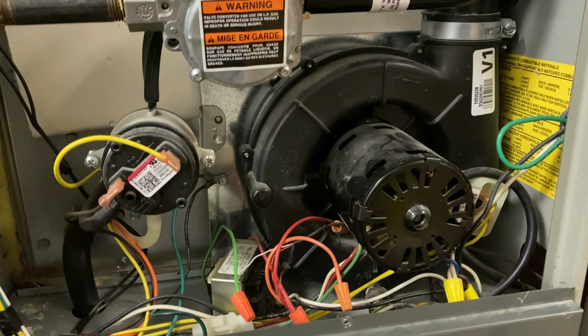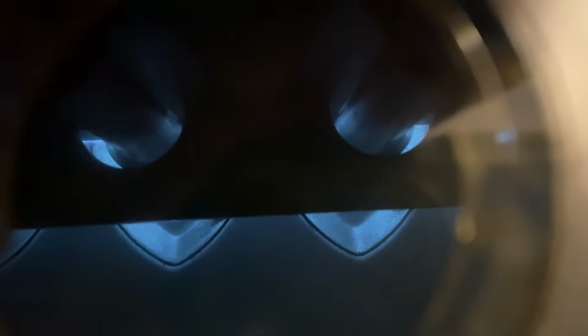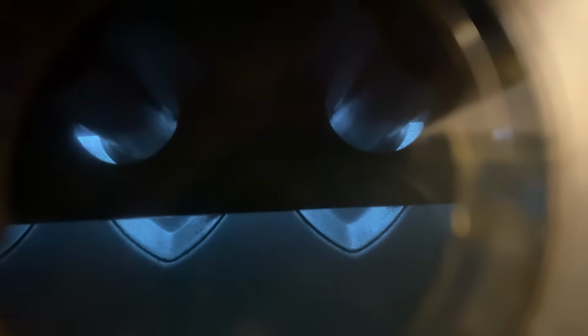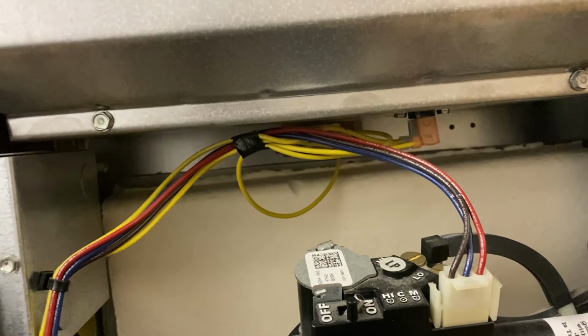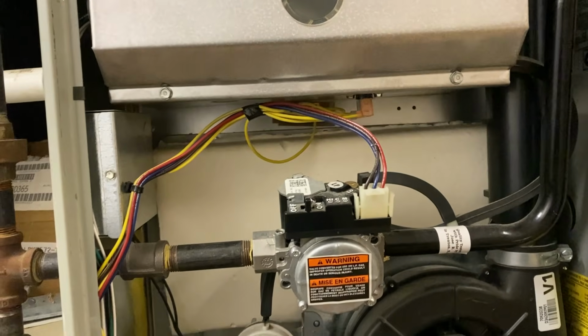Alright, so let's get it fired back up here and see if everything works. So there's the hot surface igniter, now it is working. So you see that lighting up, and then we should see some flames in here in just a moment. Gas valve should come on here. There we go. See some flames. So now we can see all the burners are fired, and they're staying lit, so that means the flame sensor is working. And as soon as it gets that heat exchanger up to temperature, our limit switch will trip and the blower will come on, and we have heat.